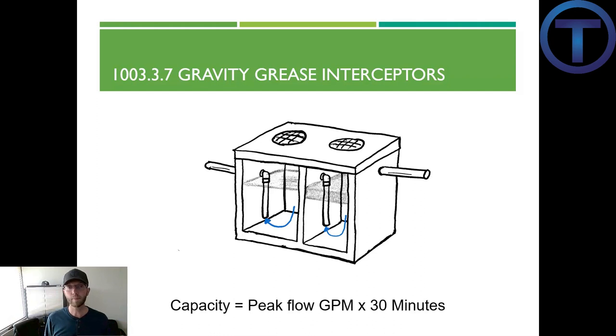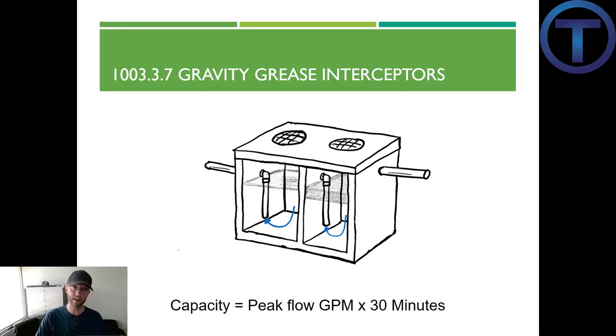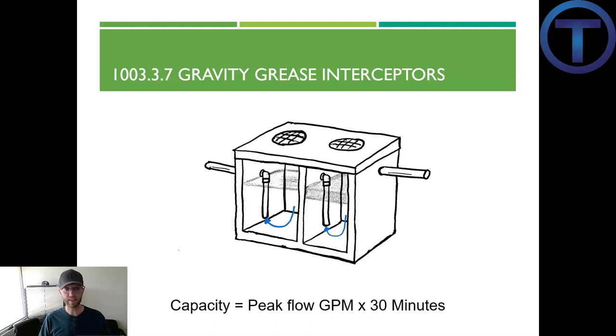Section 1003.3.7 gives us a formula for capacity. If we're trying to figure out the capacity of a grease interceptor, we take the peak flow rate in gallons per minute, multiply that by 30 minutes, and that gives us an idea of what the capacity would need to be.